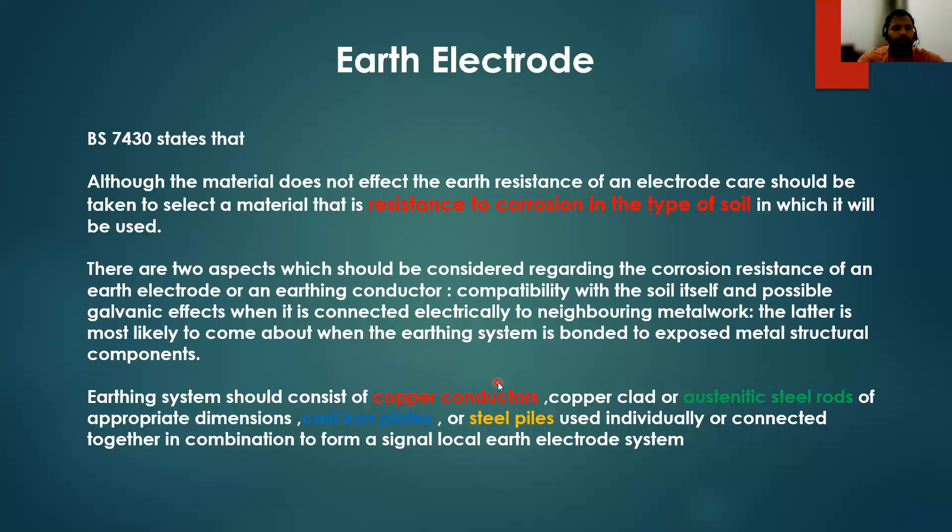Earth rod selection, earth rod electrode - what type of earth rod electrode we have to choose? According to BS 7430 standards, these are the details. Just I explain you the basic concept, what is here. Basically, earth rod material should be either copper conductors or copper clad, austenitic steel rods or cast iron plates or steel piles. These type of materials you can use as an earth rod.